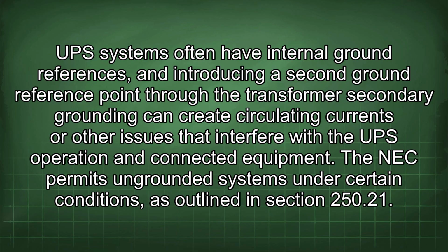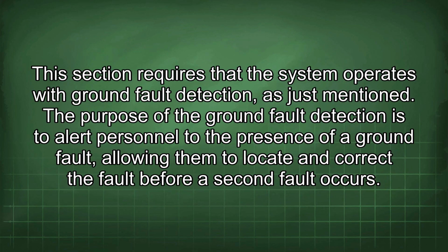The NEC permits ungrounded systems under certain conditions, as outlined in section 250.21. This section requires that the system operates with ground fault detection, as just mentioned. The purpose of the ground fault detection is to alert personnel to the presence of a ground fault, allowing them to locate and correct the fault before a second fault occurs.